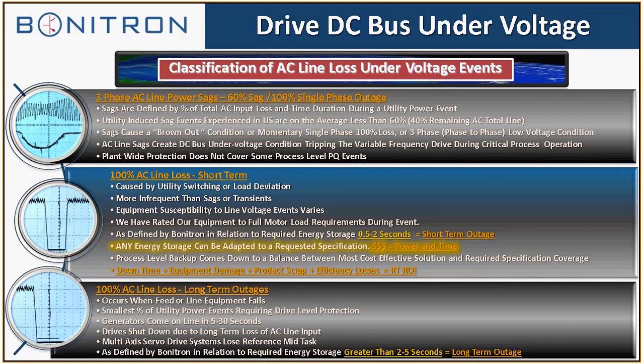The ride-through reacts to the drop in the DC bus and immediately holds up the bus so there's no change in speed or torque of the motor. Then the next category that we look at, and this is where you have to add energy storage, is a total loss of the AC input for short term. And this is usually caused by utility switching, load deviation. These are some of those internal plant issues I was talking about. Much more infrequent than sags or transients. A very small percentage of utility power events are full AC line losses.